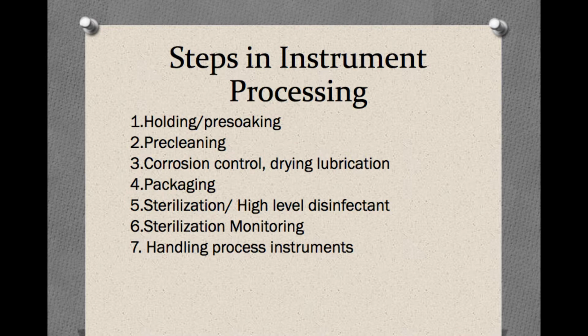So in conclusion, here are the 7 steps in instrument processing. The first step is the holding and pre-soaking step. This step is not shown in the video, but this step is only if you cannot immediately clean the contaminated instruments. You would put it into the ultrasonic. And remember, do not overfill the tank.